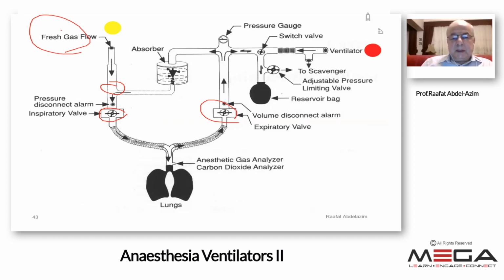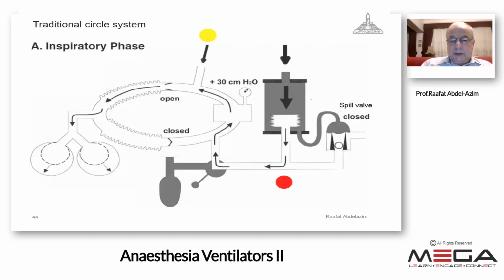So the fresh gas flow is essential for the patient, but it's not essential for the ventilator operation. This is the situation during inspiration. The inspiratory limb is open, the inspiratory valve is open, the patient's lung is inflated, the ventilator bellows is going down. It will go through the tubing into the inspiratory limb, passing through the carbon dioxide absorber to get rid of the carbon dioxide that was coming through the previous expiratory time.